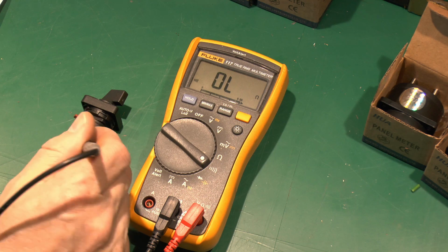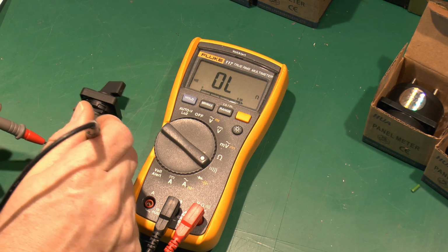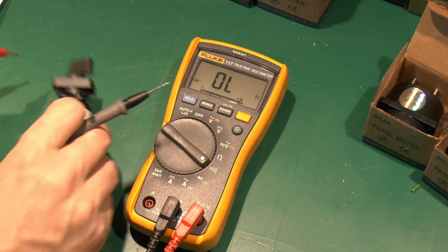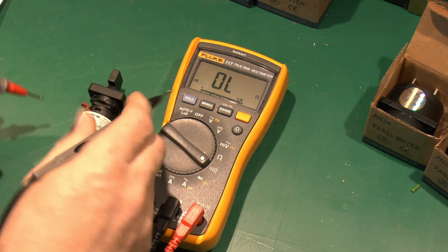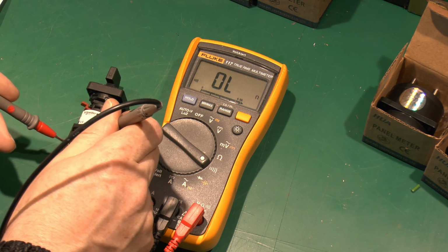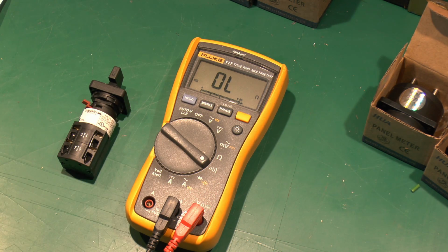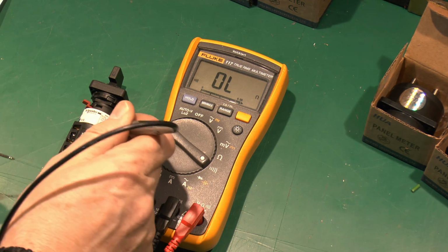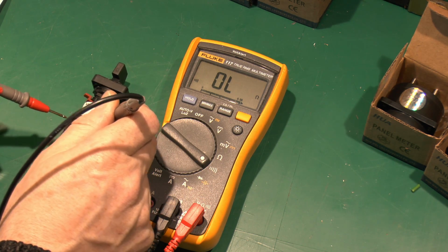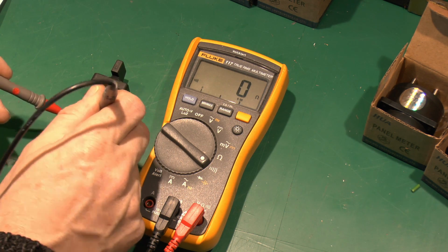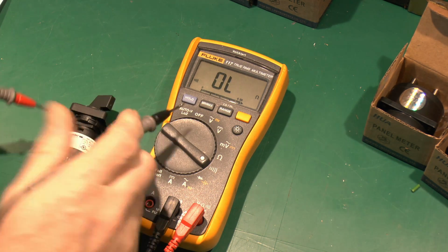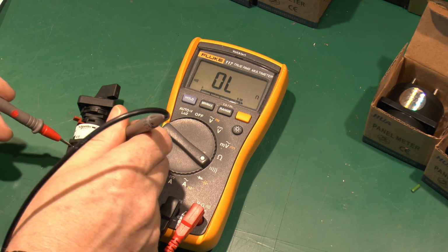Remembering that 4 is a common, so we should have continuity between the common and 7, which we do. Turn around to position number 4, and that should have gone away, which it has. Then position 4 on the selector corresponds to number 3, so should have continuity between here and 3, which we do. If we turn it back to one of the other positions, yep, that has gone away.